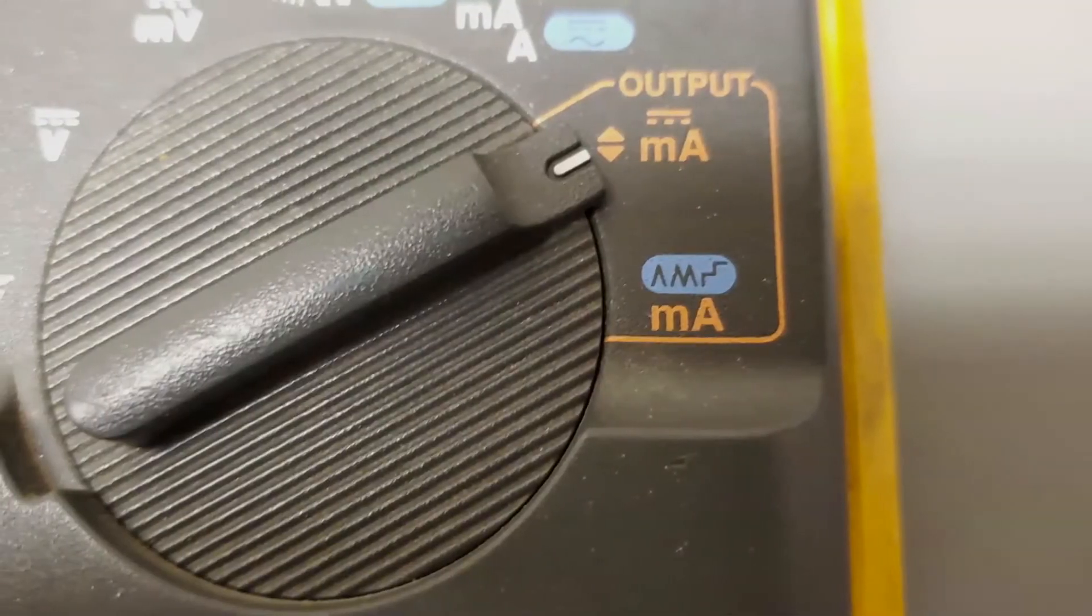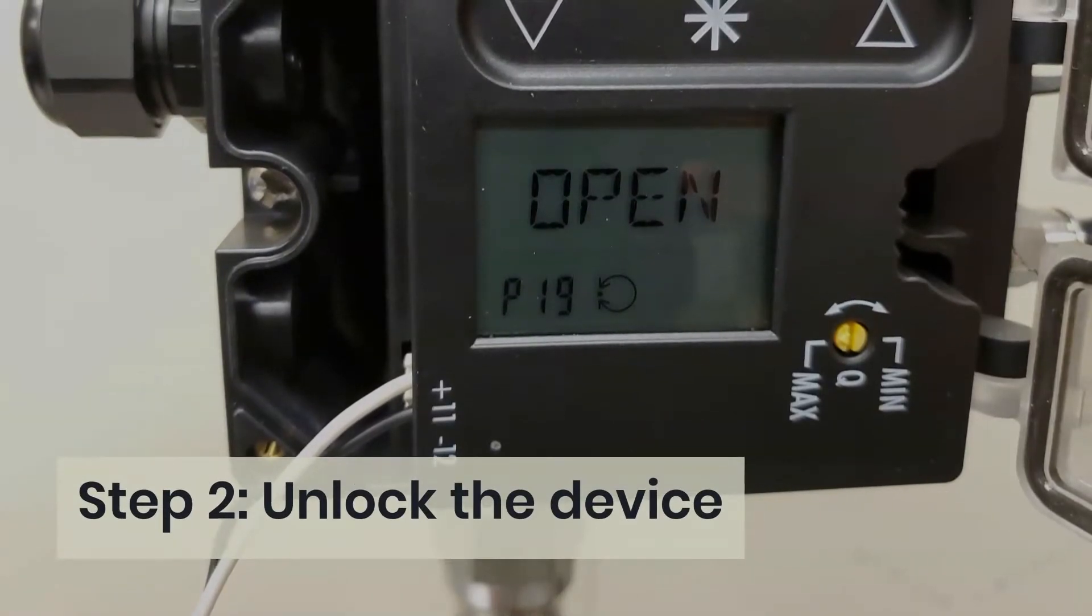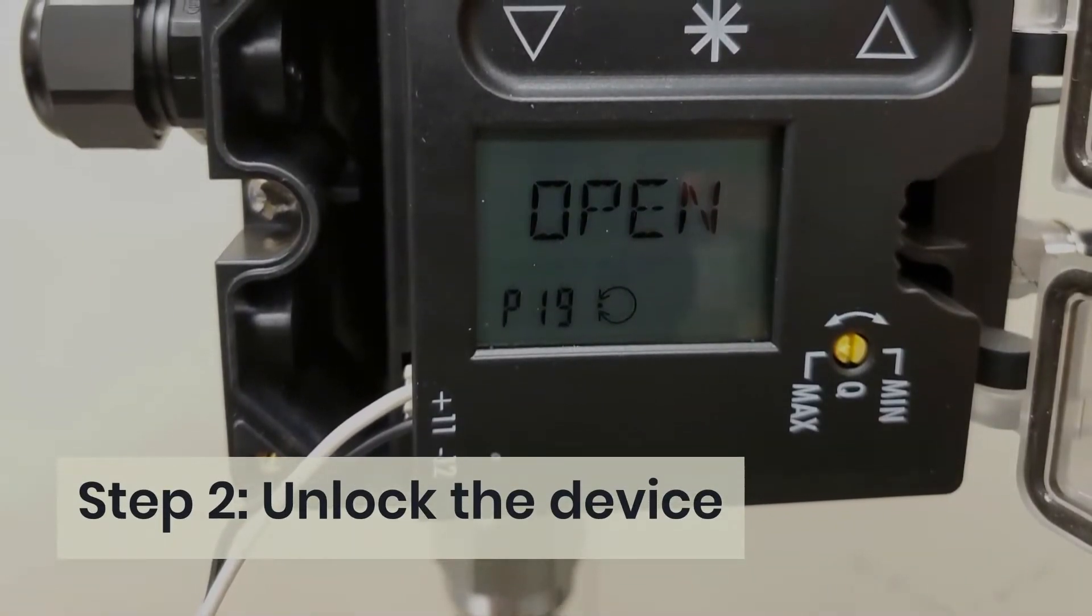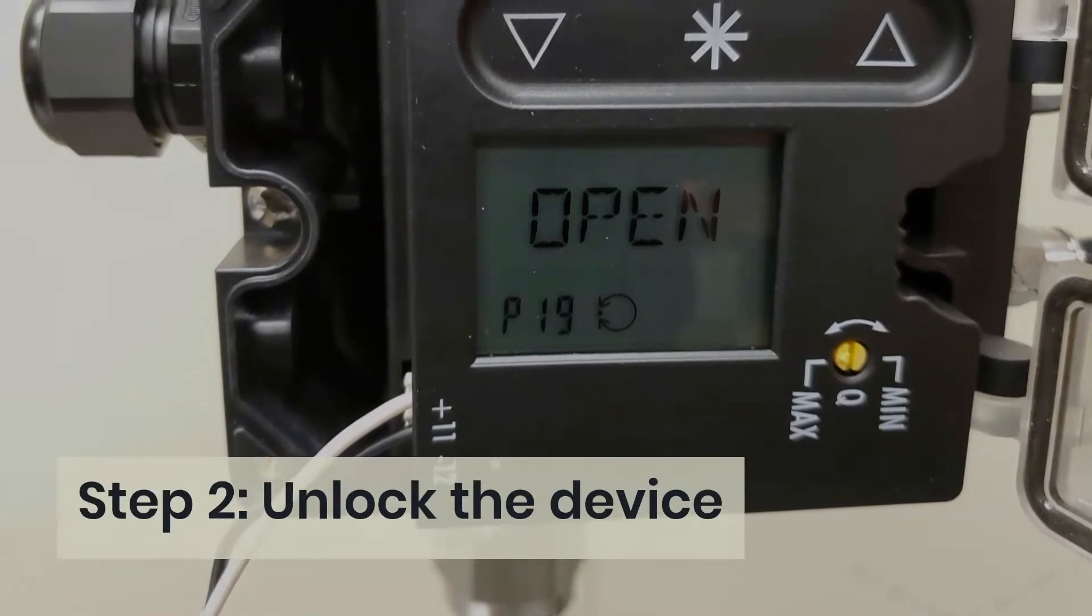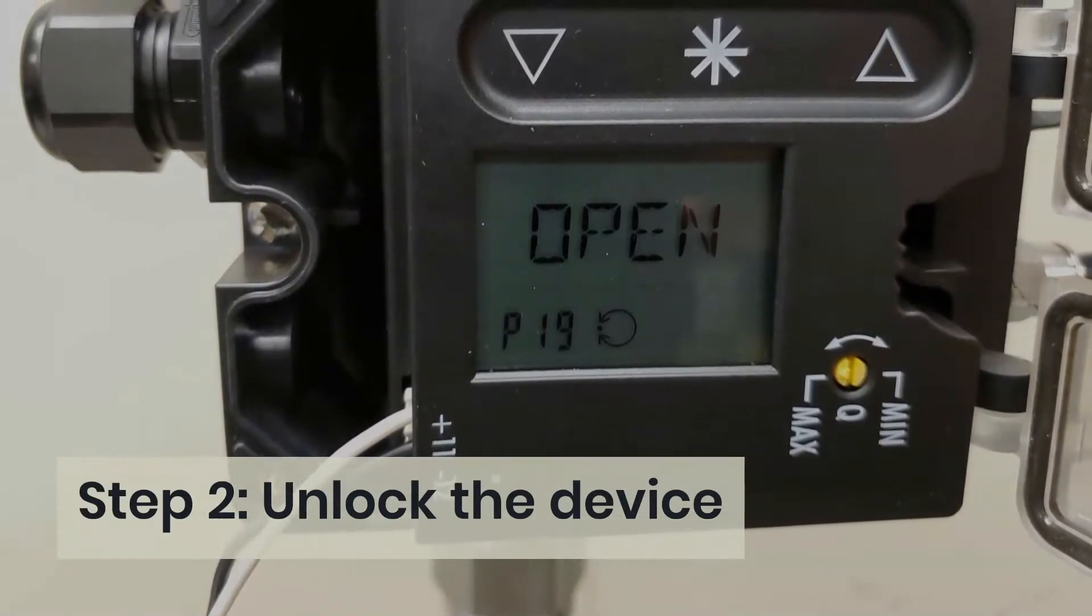Step 2: Unlock the device. Before changing parameter settings, configuration must be enabled first by selecting code P19. If no settings are entered within 3 minutes, the enabled configuration function becomes invalid. Press the down or up arrow until code P19 appears.